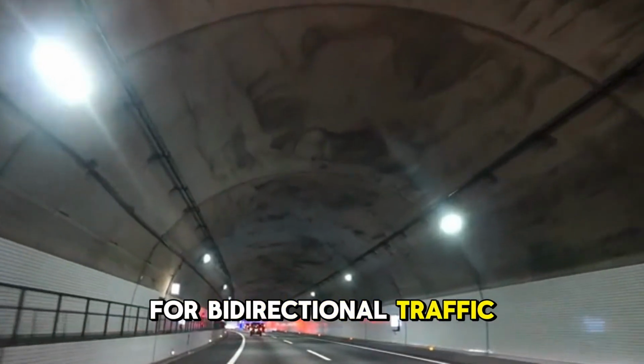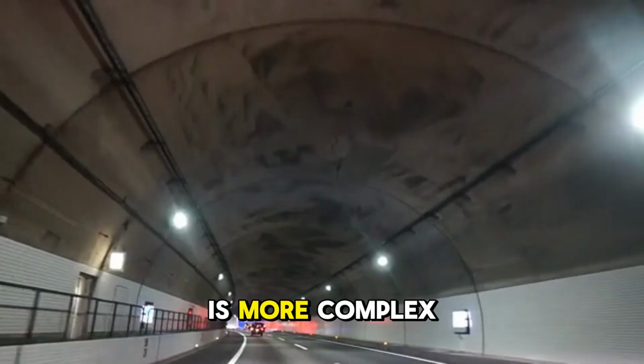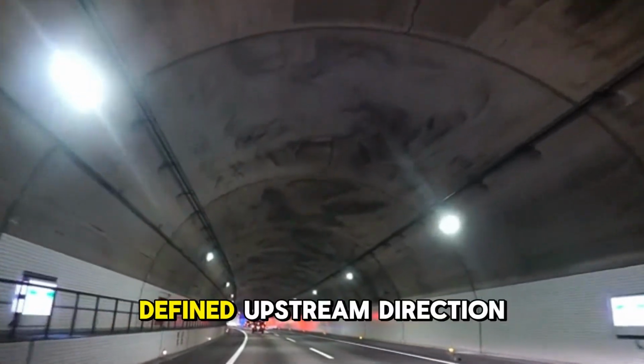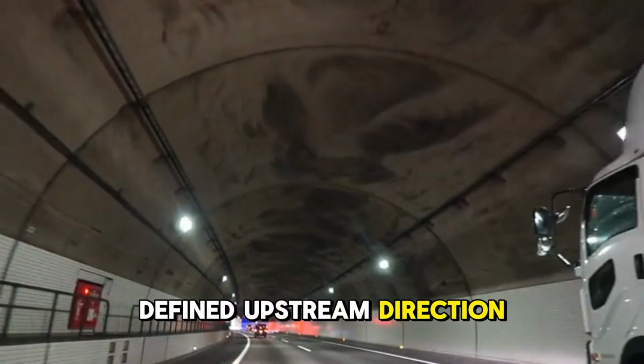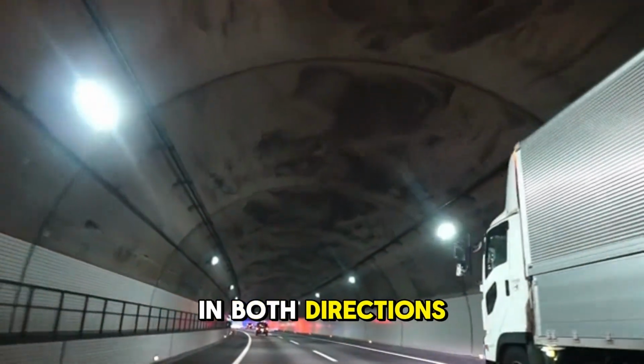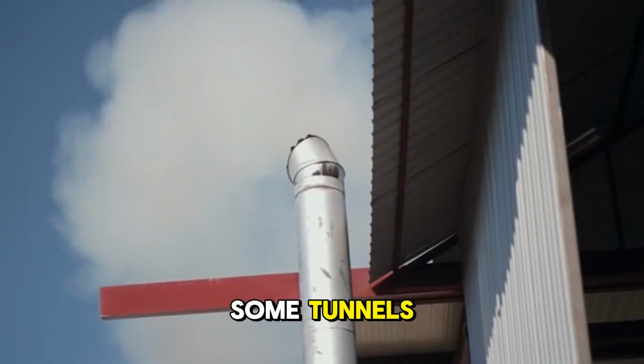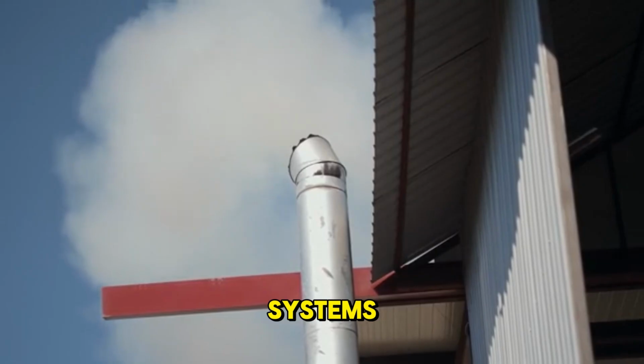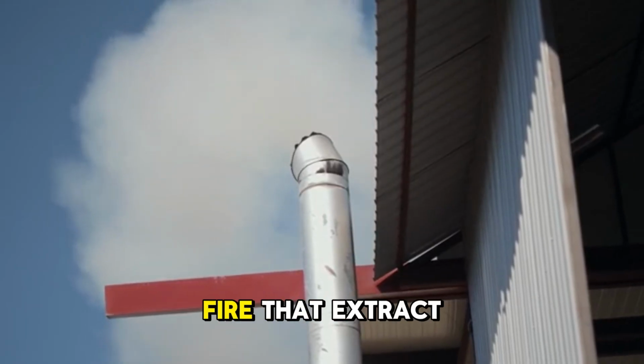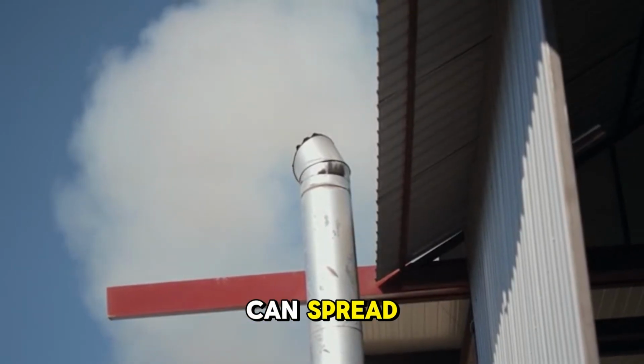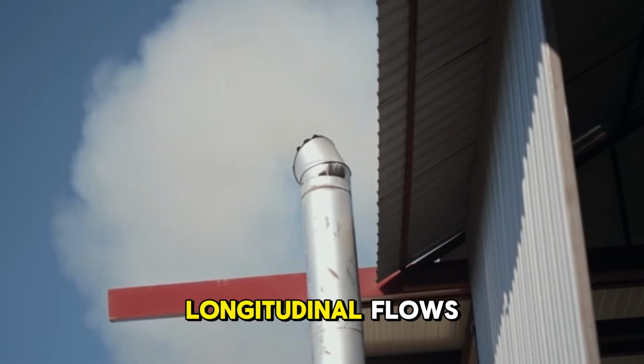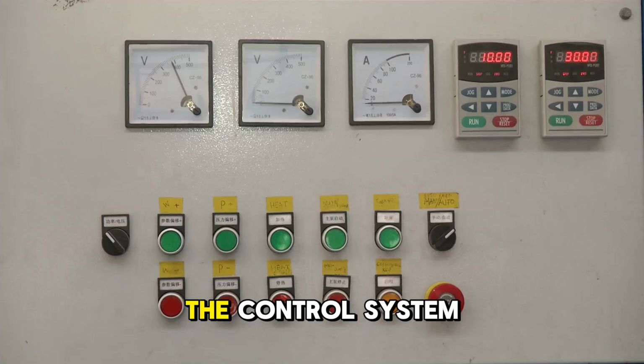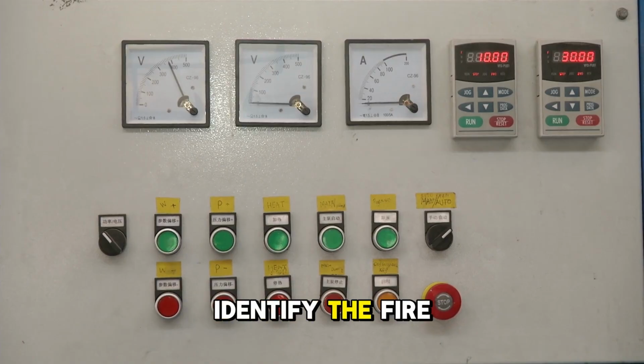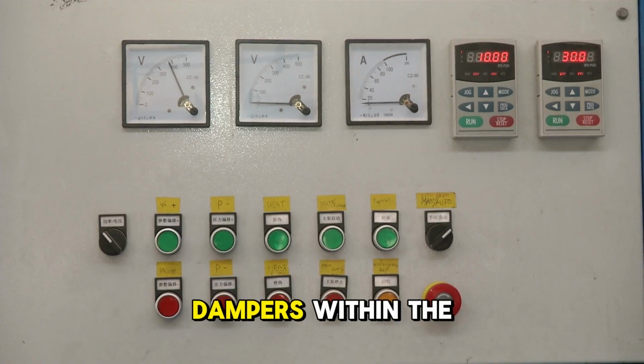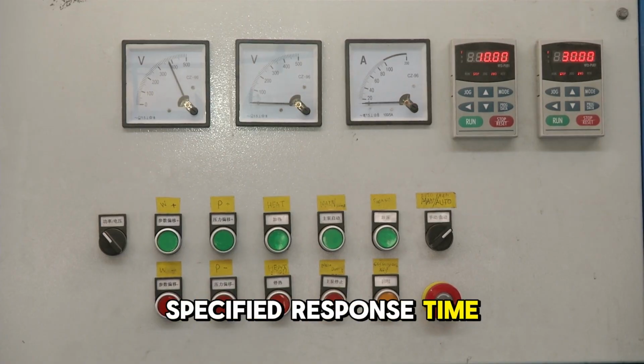For bidirectional traffic, emergency ventilation is more complex because there is no defined upstream direction. Smoke can spread in both directions from the fire. Some tunnels use point extraction systems, ceiling exhaust dampers near the fire that extract smoke before it can spread, combined with directed longitudinal flows. The control system must identify the fire location from detector inputs and open the appropriate dampers within the specified response time.